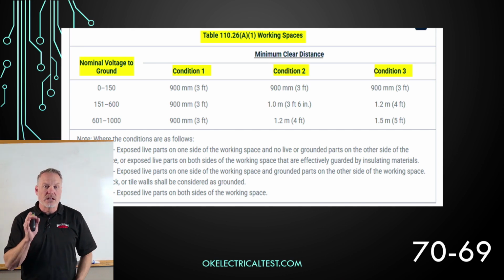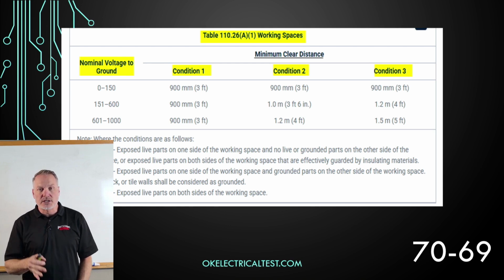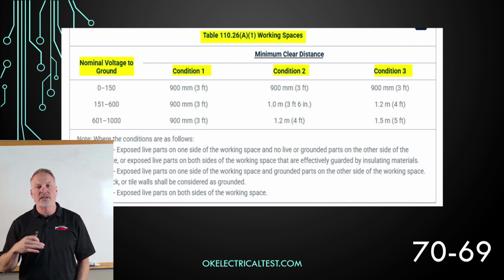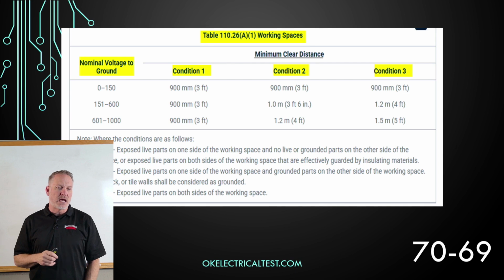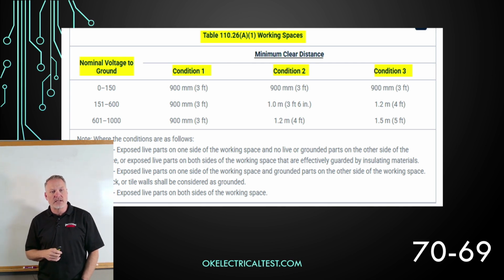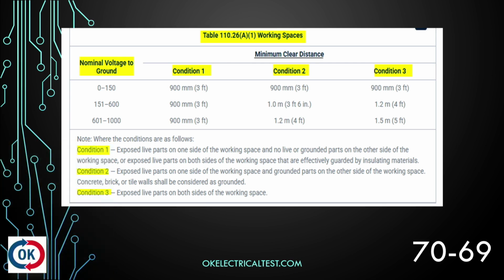And then we have a column that's condition 1, condition 2, and condition 3. That information's useless to us unless we know what those conditions are. Down below the table, under notes, these are our conditions. Condition 1 is I've got live parts on one side of the working space and no live or grounded parts on the other side of the working space.